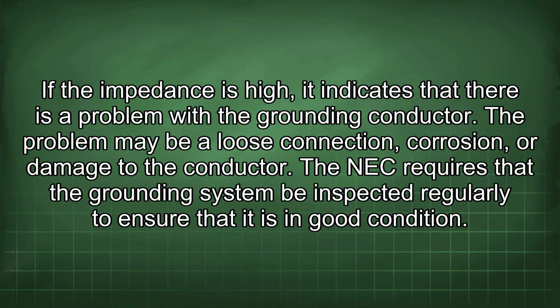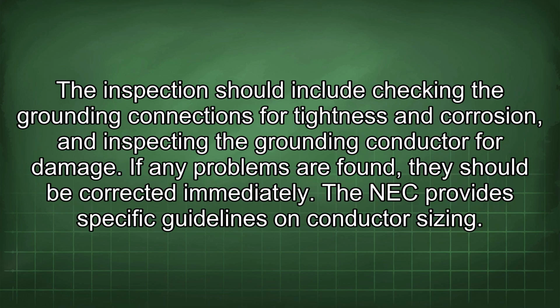The problem may be a loose connection, corrosion, or damage to the conductor. The NEC requires that the grounding system be inspected regularly to ensure that it is in good condition. The inspection should include checking the grounding connections for tightness and corrosion and inspecting the grounding conductor for damage. If any problems are found, they should be corrected immediately.